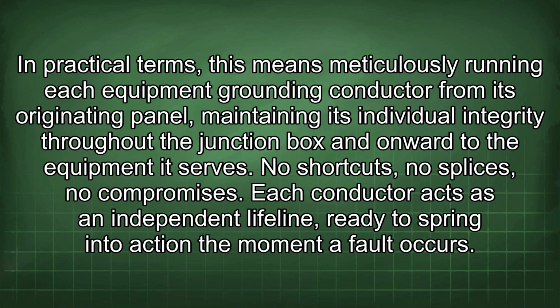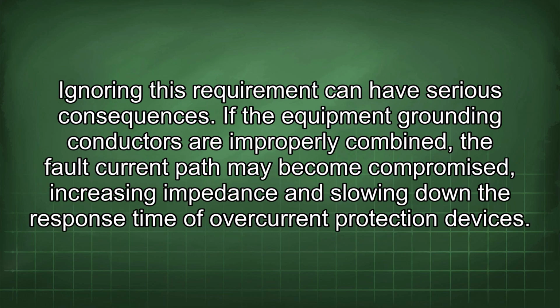In practical terms, this means meticulously running each equipment grounding conductor from its originating panel, maintaining its individual integrity throughout the junction box and onward to the equipment it serves. No shortcuts, no splices, no compromises. Each conductor acts as an independent lifeline, ready to spring into action the moment the fault occurs. Ignoring this requirement can have serious consequences.